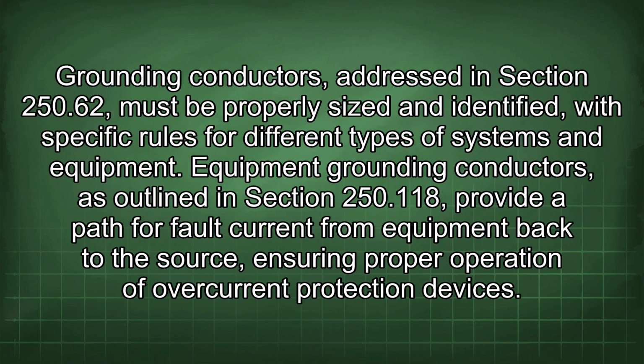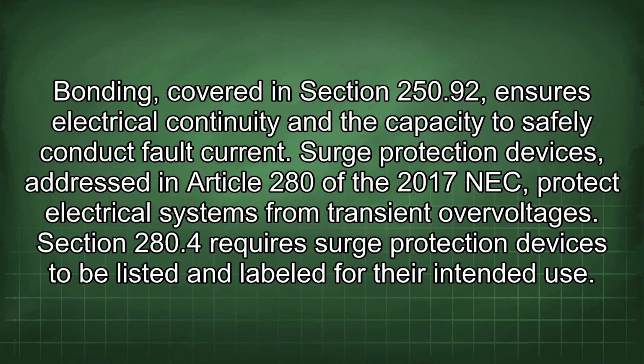Grounding conductors, addressed in Section 250.62, must be properly sized and identified with specific rules for different types of systems and equipment. Equipment grounding conductors, as outlined in Section 250.118, provide a path for fault current from equipment back to the source, ensuring proper operation of overcurrent protection devices. Bonding, covered in Section 250.92, ensures electrical continuity and the capacity to safely conduct fault current.